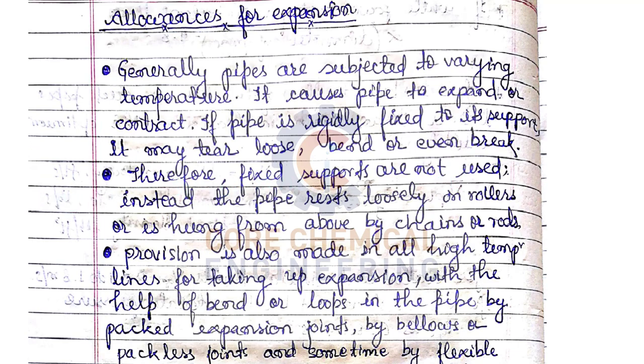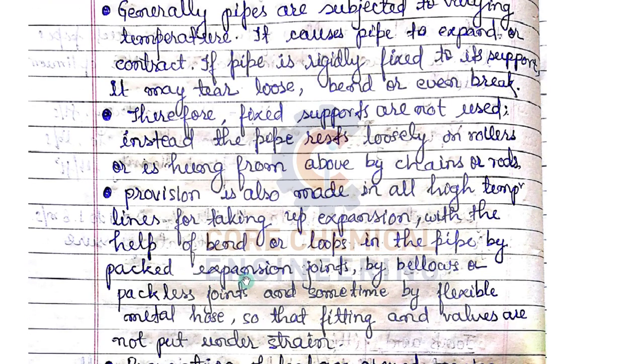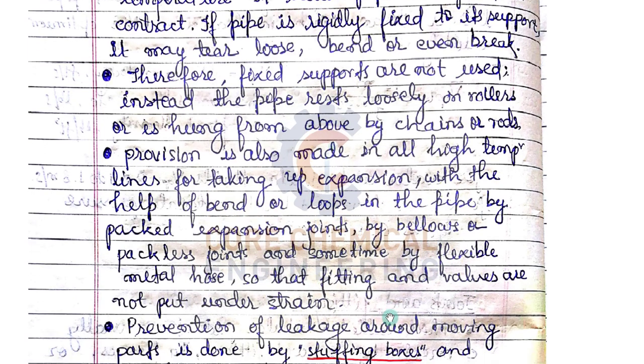Instead of fixed supports, pipelines rest on base plates or are supported by spring-type or T-linear supports. Provisions are also made in all high-temperature lines to accommodate expansion with the help of bends or loops in the pipe, packed expansion joints, bellows, packless joints, or flexible metal hose, so that fittings and valves are not put under strain.